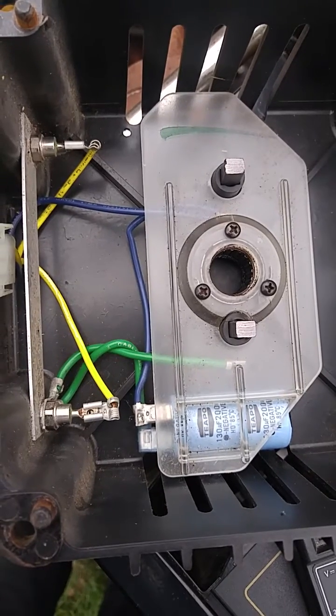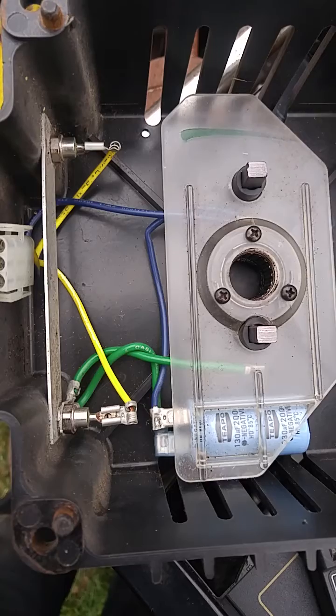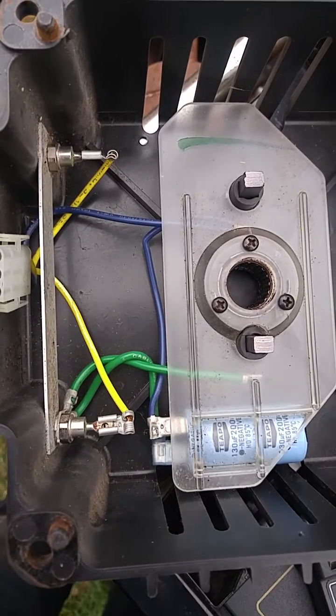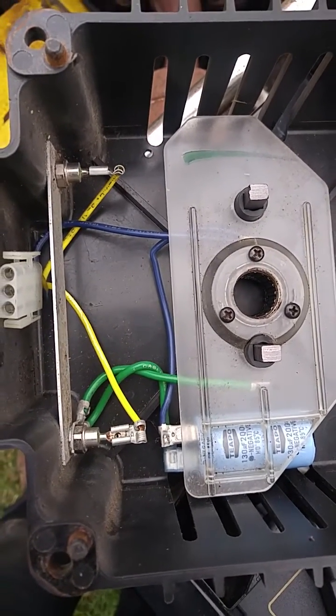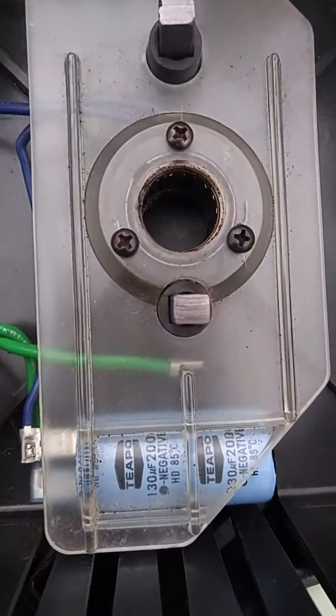With that low 1.7 voltage value, I'm guessing maybe I could try to re-magnetize, re-flash, or whatever that's called. But I'm just going to hold off on doing that and focus on replacing the capacitor.